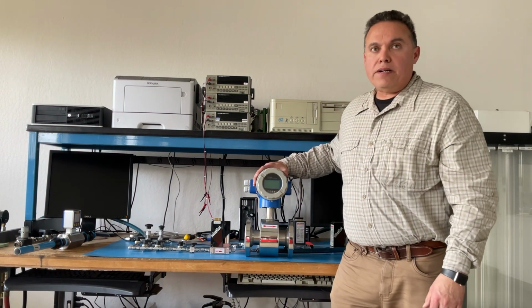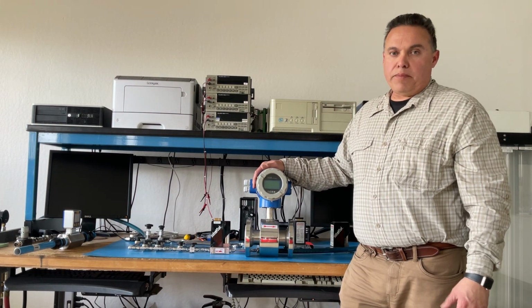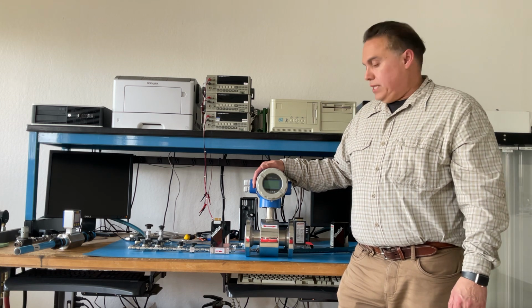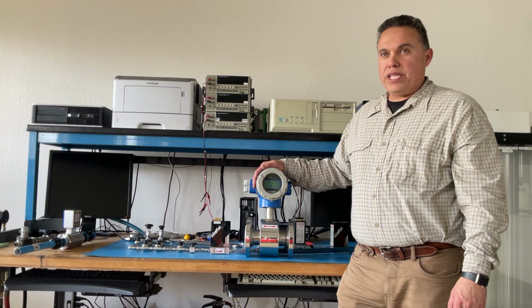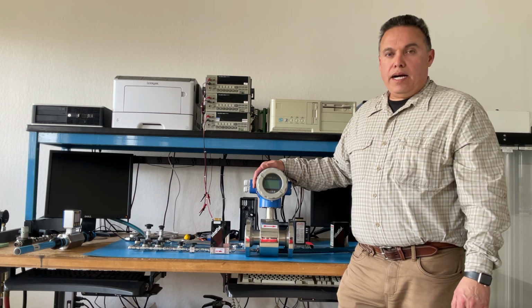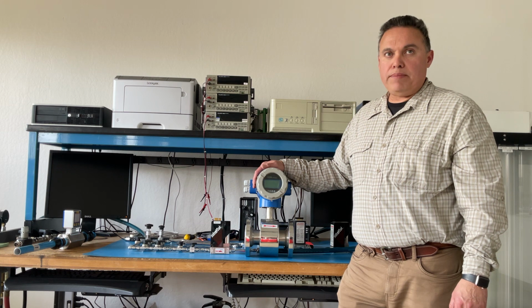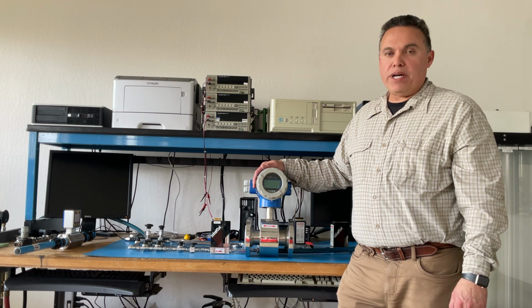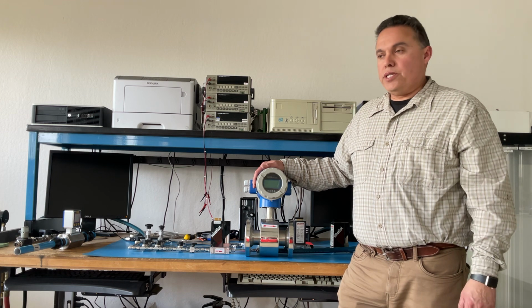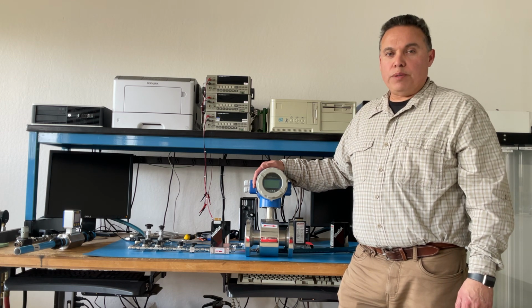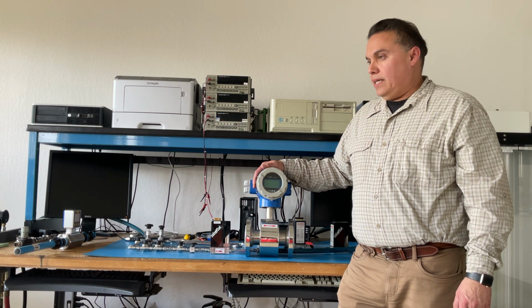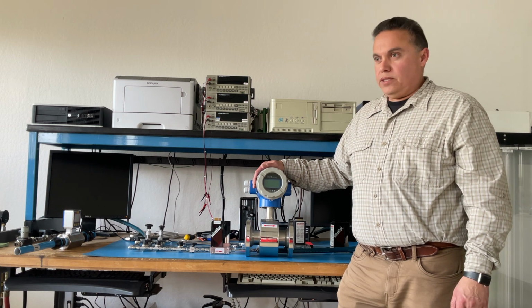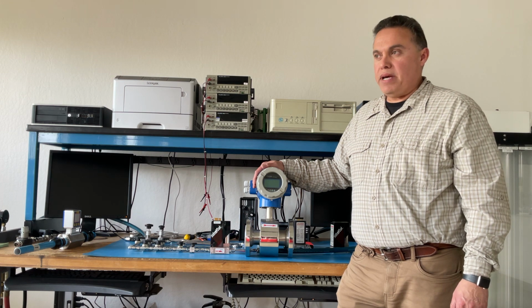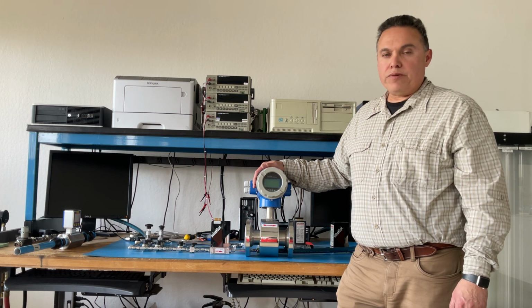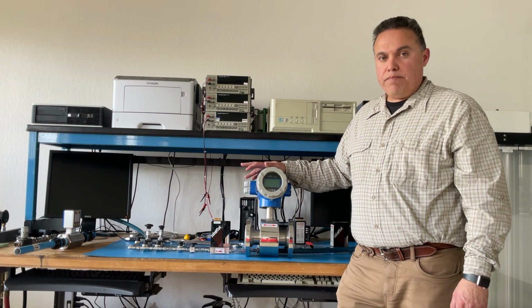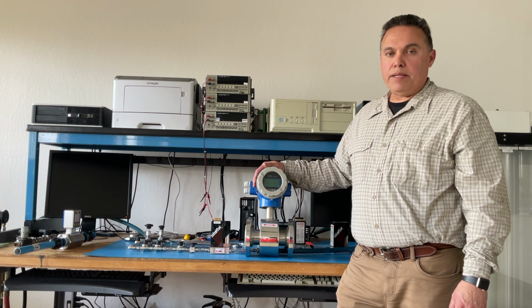The way we calibrate this meter is we calibrate it like everybody. We characterize the meter and sensors, and we use that calibration as a baseline. That's where most manufacturers stop. What we do in addition to that, to get even better accuracy, just because we can, is we use a trim factor, and this trim factor is applied to the meter calibration, so that we correct based on frequency separation or frequency error between this meter and the reference meter that we use to calibrate it.